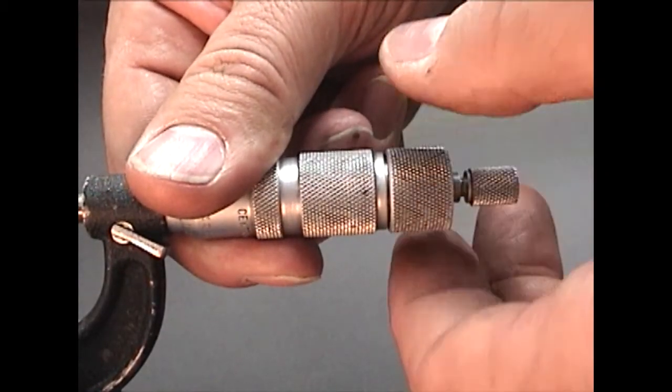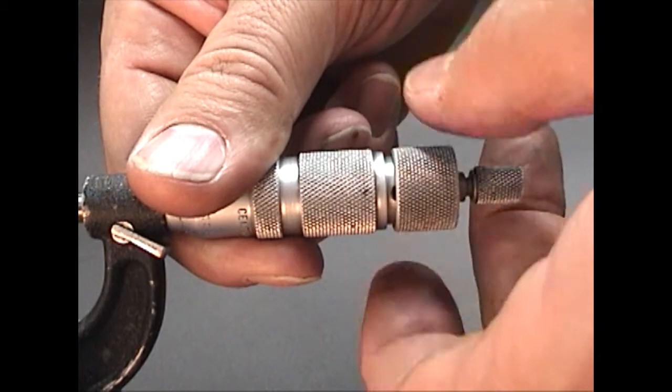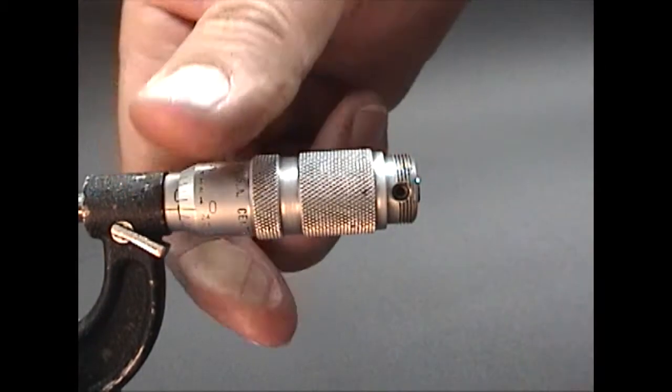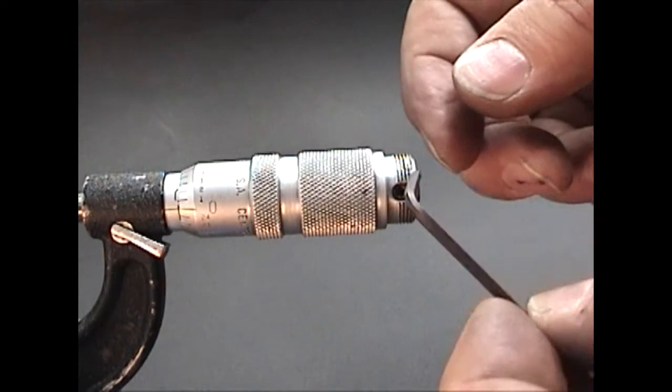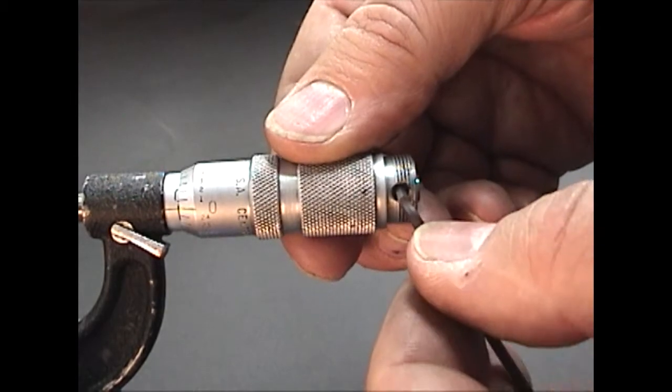The thimble ratchet cover unscrews from the thimble. This exposes the thimble set screw. Loosen the set screw.